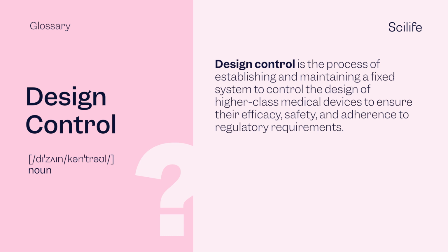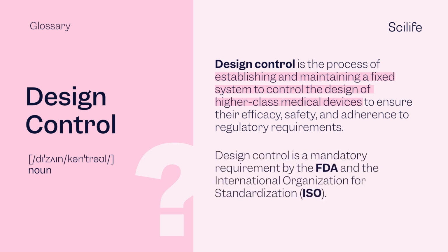Design control is the process of establishing and maintaining a fixed system to control the design of higher-class medical devices to ensure their efficacy, safety, and adherence to regulatory requirements. Design control is a mandatory requirement by the FDA and the International Organization for Standardization, ISO. The design control process has to be written or electronically documented to show how it addresses the regulatory requirements.